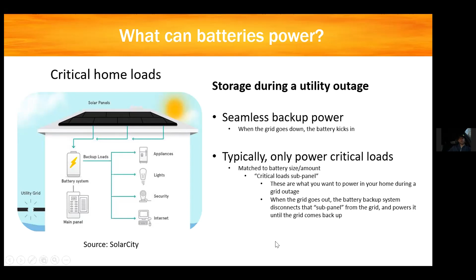There's also another box that goes on called the backup gateway. It operates as an automatic transfer switch, so when the grid goes out, it tells the battery to turn on and your solar will run. In a grid outage, if you don't have a battery, your solar will not operate — it needs to see the grid or some source of power to operate.